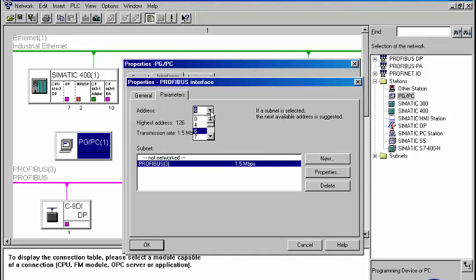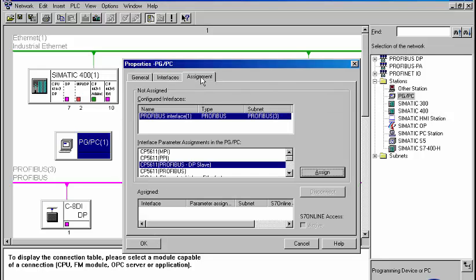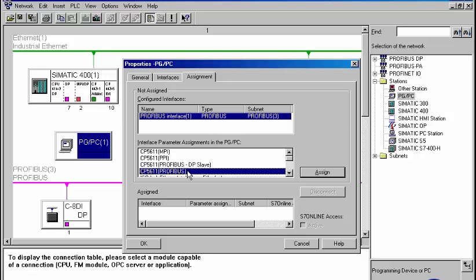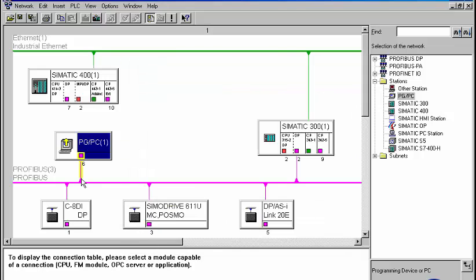The address field automatically displays the remaining free addresses. Now the corresponding network card and configuration must be assigned to the interface. We select CP5611 PROFIBUS and allocate it to the new interface. At the connection between the programming device and the bus system, now shaded in yellow, we can recognize that the S7 online access for the selected interface has been activated.